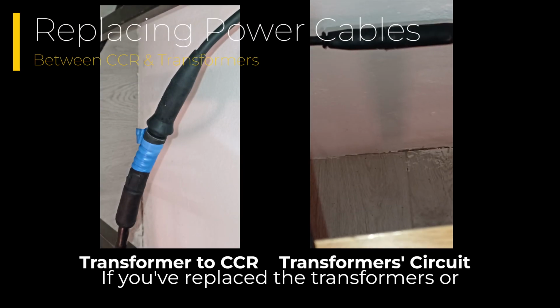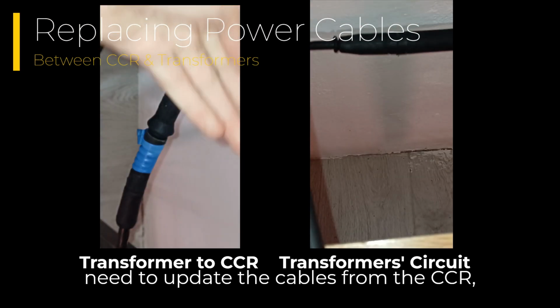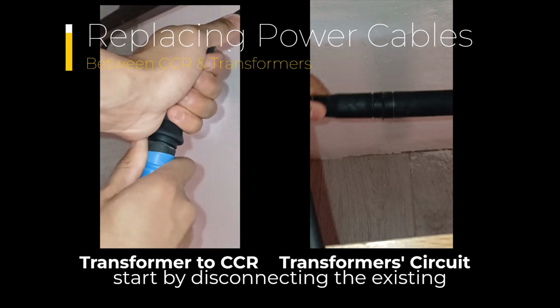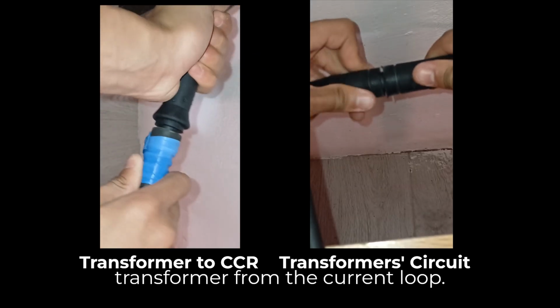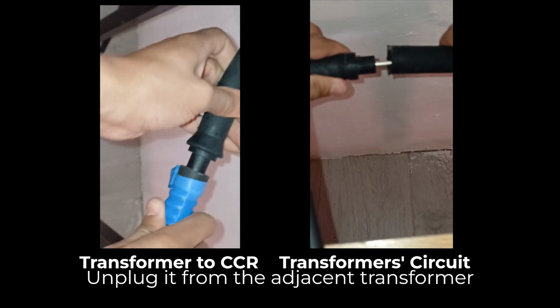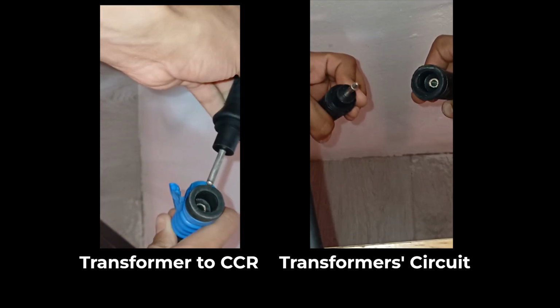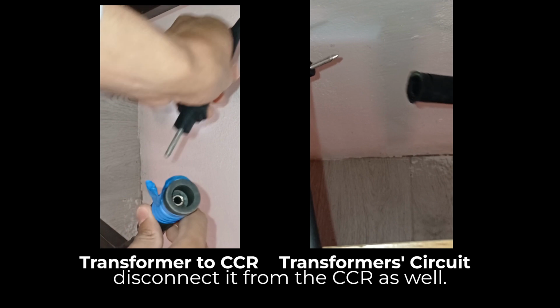If you've replaced the transformers or need to update the cables from the CCR, start by disconnecting the existing transformer from the current loop. Unplug it from the adjacent transformer and, if it's at the end of the loop, disconnect it from the CCR as well.